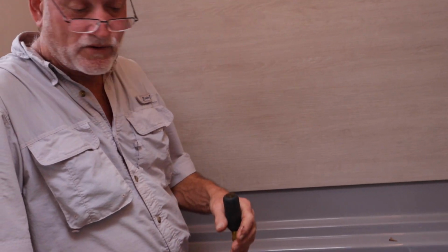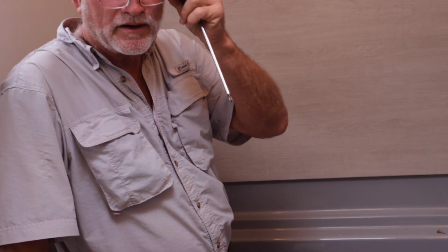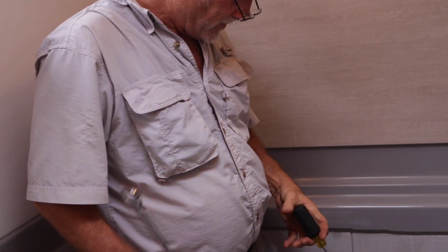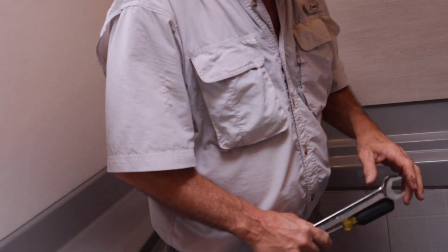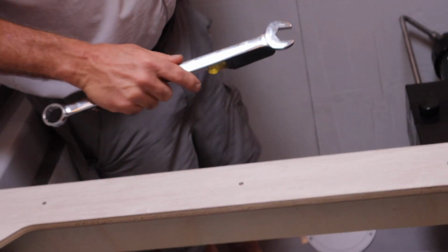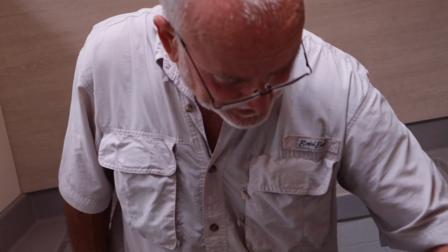There's a lot of metal parts threaded into it. Now, the external parts are metal, like you see the stainless steel tubing. That's easy to replace after a while without having to break into the system, because stainless steel will even pit and start getting holes in it. But if it leaks, unless it's a hose clamp like this, which is easy to grab and tighten down, anything where metal parts go into here is going into plastic parts. It's either O-ring or Teflon tape. We have to take it apart and reassemble it with the proper O-ring or Teflon tape.